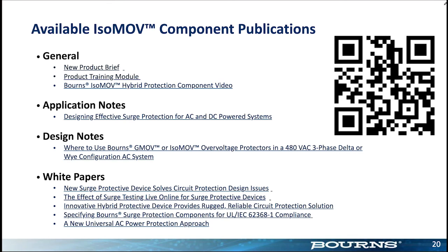Right. The question was about whether the clamping voltage can be made lower, and the answer is yes. The clamping voltage does get lower because now you have more surface area, with two units instead of one. Again, I would point to the white paper on selecting the MOV. That white paper describes what you can expect to see for the clamping voltage if you put two in parallel. Okay, Thomas, you and I will have to talk about that offline.